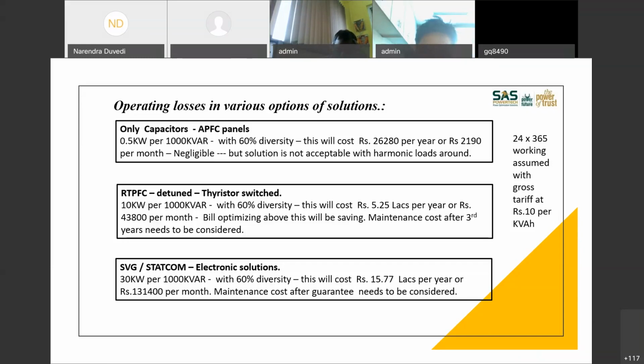With all that, for an RTPFC panel, your loss will be about 10 kilowatt for 1000 kVAr. Again, I am assuming 60% diversity, in the sense that all 1000 kVAr will not be connected simultaneously because of some load variations. Probably a few of them may get disconnected frequently. So I am assuming only 60% diversity. With that, this panel will consume about 5.25 lakh rupees worth of electricity per year, or 43,800 rupees per month. So whatever you are going to save after installing this 1000 kVAr panel, 43,800 rupees of it will be consumed by the panel itself. So you have to consider this before actually calculating the payback.